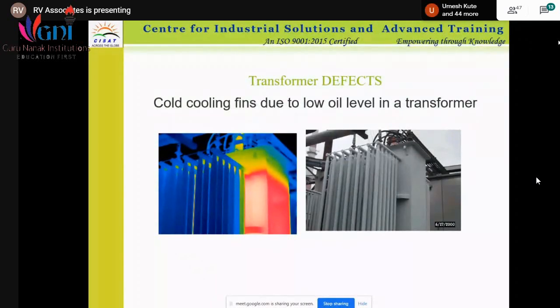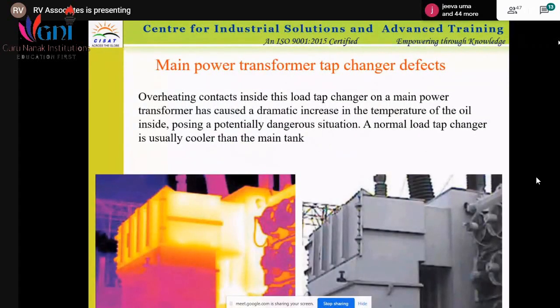This is the cooling fins. See, some part of the cooling fins is getting heated. Why is it getting heated? It may be because some fins are blocked, oil circulation is not proper, and there may be a rise in hotspots in the transformer. So this has been detected by thermography. Tap changer: the same thing, if there is an imbalance in the fault, or if there is continuous changing in the OLTC, it will lead to arcing. That arcing may lead to a rise in temperature. So that particular part has been shown by thermography.